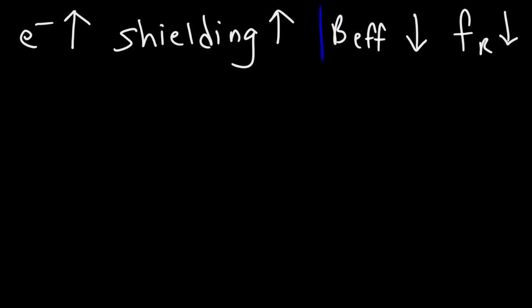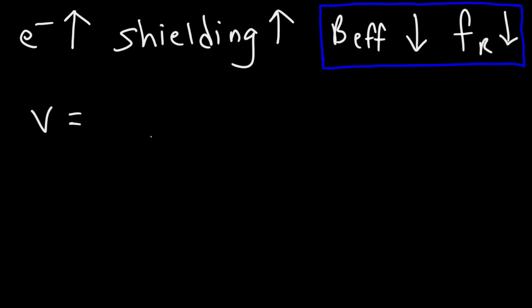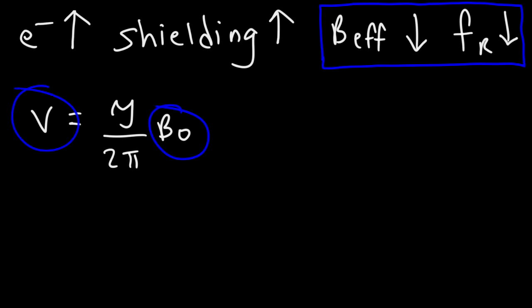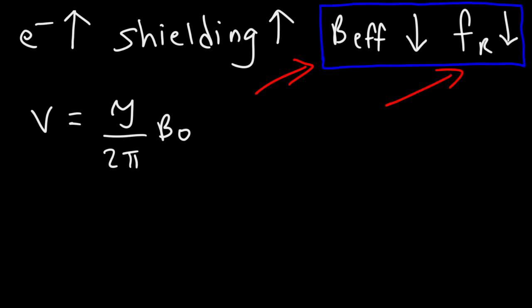You might wonder why magnetic field and frequency are proportional. There's a formula that explains it: the operating frequency of an NMR spectrometer equals the gyromagnetic ratio — which depends on the nucleus, whether it's hydrogen or carbon — divided by 2π, times the applied magnetic field. So if the magnetic field goes up, the operating frequency required to achieve nuclear magnetic resonance must go up as well. Thus, if the effective magnetic field the nucleus feels decreases, the frequency to achieve resonance decreases too.